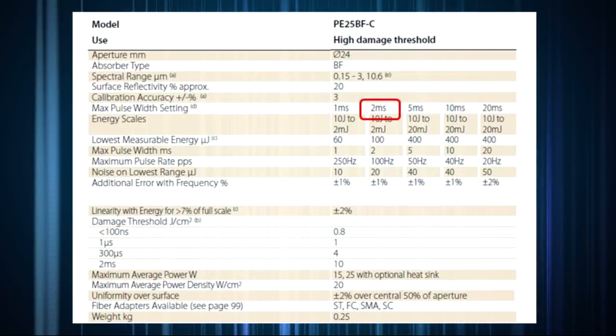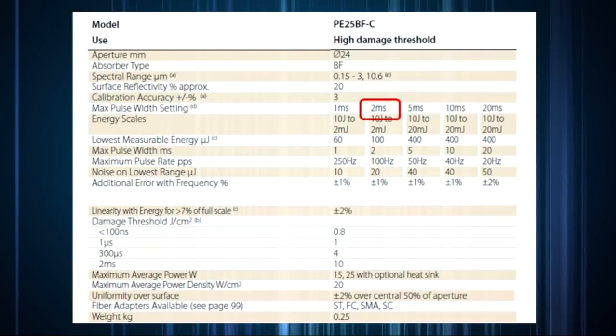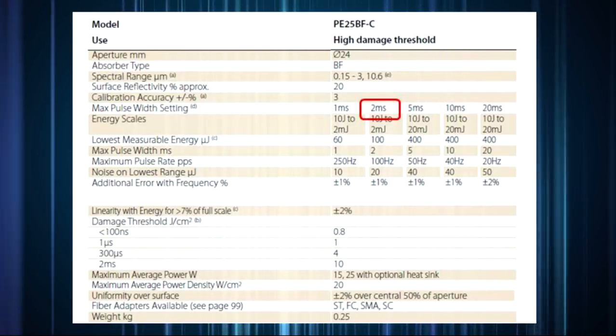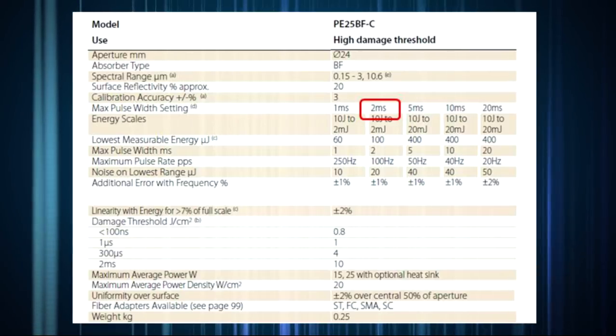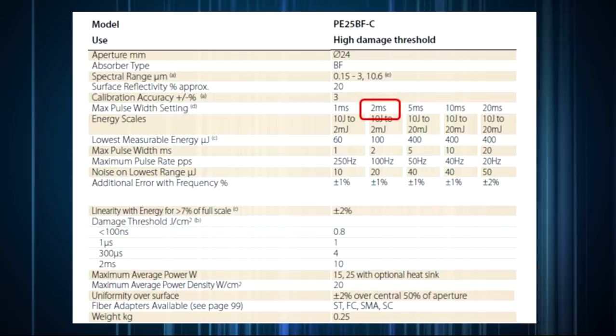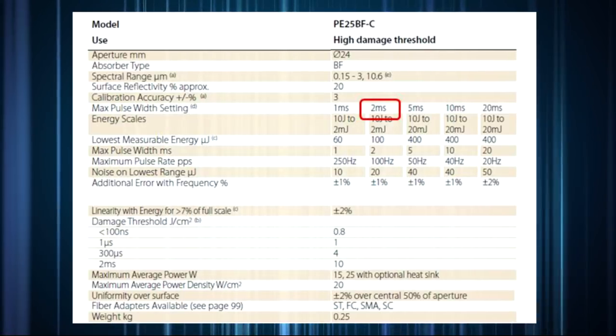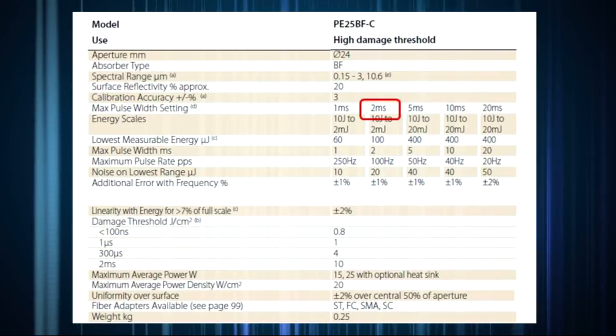When the user sets the maximum pulse width, for example 2 milliseconds, this automatically determines the integration time. Even if the laser's pulse width is actually only 3 nanoseconds, the sensor will hold the voltage for 2 milliseconds in this example and integrate it, meaning collect and measure it.